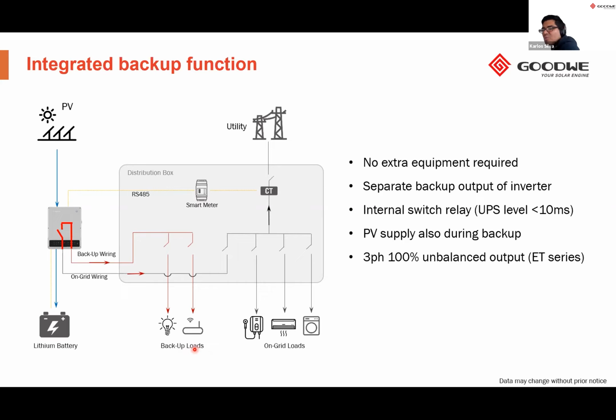But just be wary that the backup load does have restrictions on how much power you can connect on each phase. Our backup function, well, it switches into backup mode in less than 10 milliseconds. So we can say that it is UPS level, but we wouldn't say that it's UPS grade. UPS grade means that you have a certificate certifying that it is allowed to be used for medical equipment. I would not recommend that you connect any type of life-saving device or any type of medical equipment to the backup output or use our inverters for these types of applications.